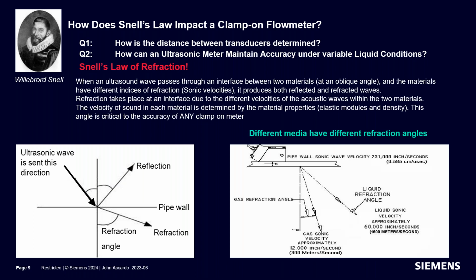And the amount that the sonic beam changes direction in the flow stream is relative to the speed of sound of the fluid that we're measuring. And that's a variable. Fluid can change speed of sound due to pressure, temperature, and liquid chemistry. Think about an application on a hydrocarbon pipeline, where you might be flowing gasoline one day, then diesel fuel, in between jet fuel, and then maybe some fuel oil. That represents quite a range of speed of sound, and the refraction angle is going to change with each of those fluids. It's critical for a clamp-on flow meter to maintain its accuracy, to be able to detect that change in beam angle and determine what it is, because that angle is used in the calculation of flow.